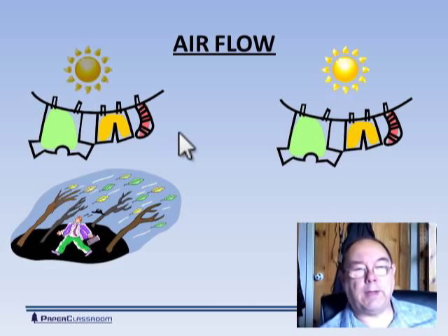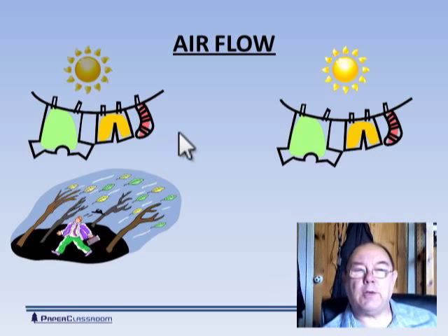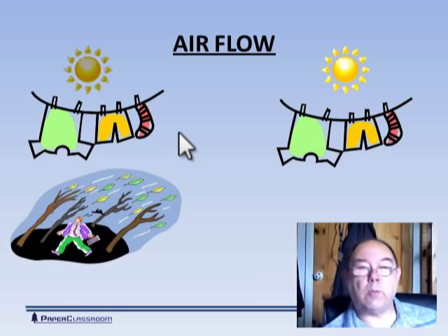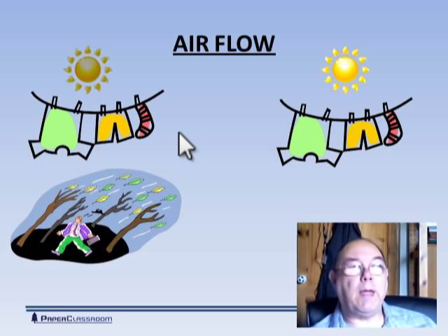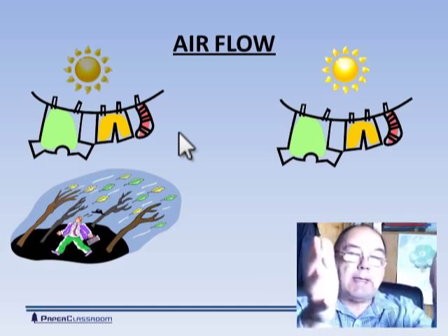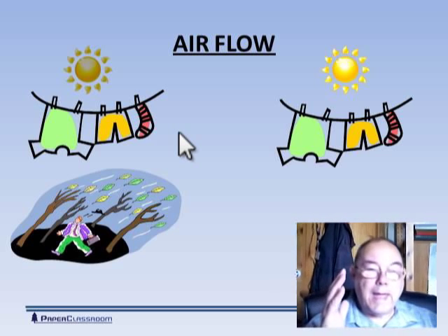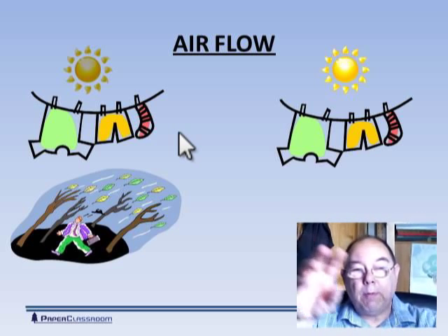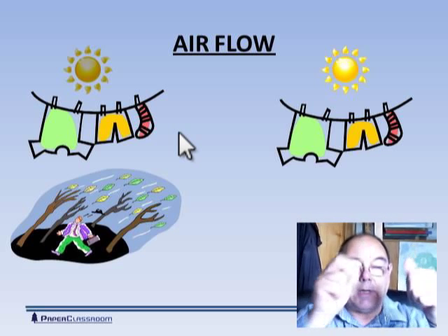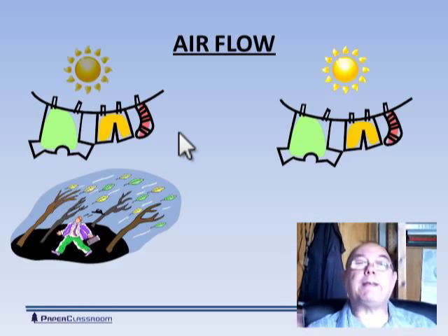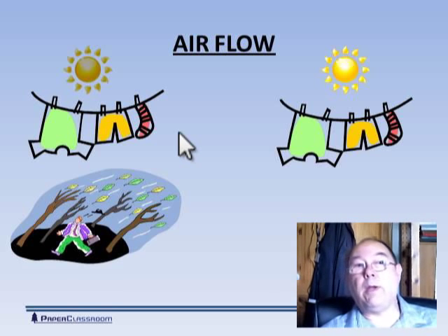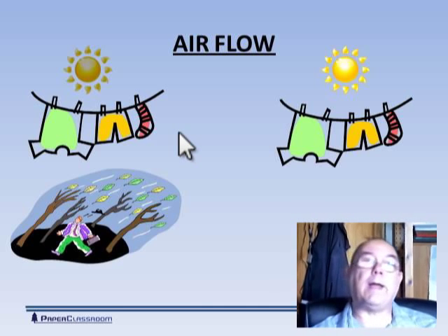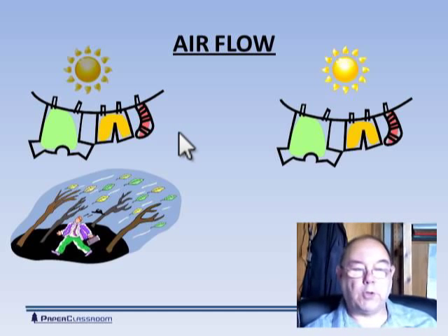There's a whole lot more to the science of drying — topics like pocket ventilation. If you look at very old paper machines, they were completely open. The steam evaporated from the paper and filled the areas between the drying cylinders. On the edges of the machine there were drafts, so that air would be replaced with dry air. But in the centre of the machine it would stay moist, so the edges would dry faster than the middle. That would cause either a break because the edge became too taut, or if you controlled edge tension, the middle would become too slack, resulting in creasing problems and moisture profile problems.